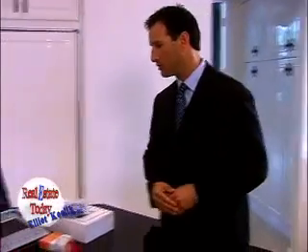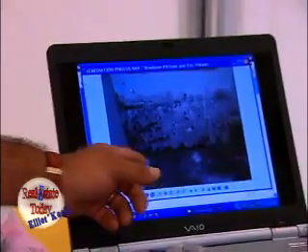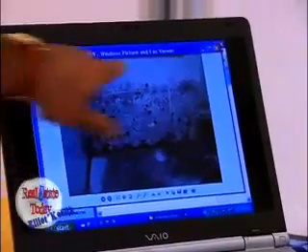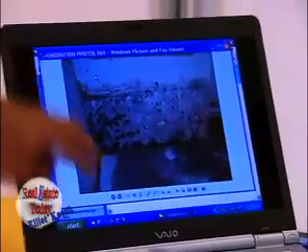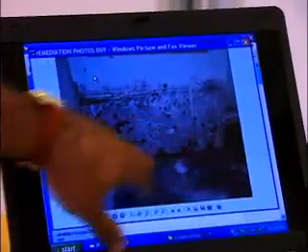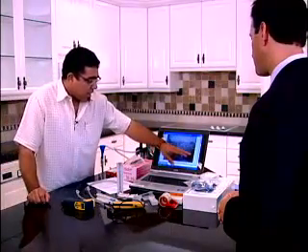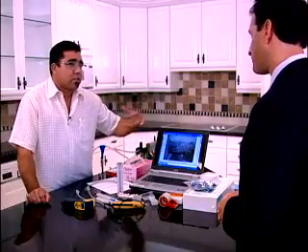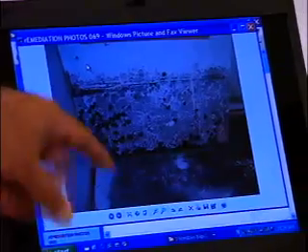These are locations — this is typical of what you'll see on an air conditioning duct register. This is the handler right here where you have your duct attachment to the top of the handler. And here we have all of this mold growth, which is from the condensation. There's a leak there — you can see there's no tape along there connecting the handler to the ductwork. Air is escaping through here, and as it escapes, it carries moisture which condenses on the ductwork and feeds these microbial organisms.